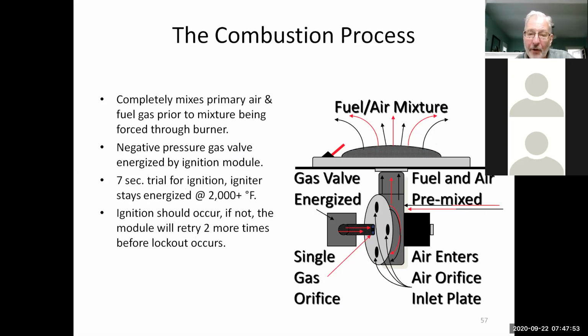If it doesn't light, it'll try 2 more times. If it doesn't light on the 3rd try, it'll go into a 1-hour soft lockout. And after 1 hour, it'll go to 3 tries again. So you could have a situation where you get a no heat call, and by the time you get there, the thing's running. It's just because of the retries after that 1-hour period.